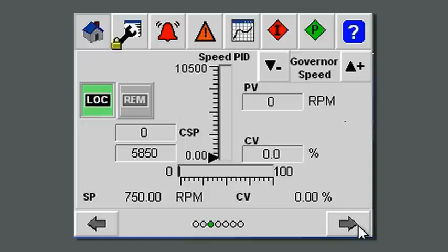The speed PID is the one that actually controls the steam turbine speed. On this screen you see everything about the speed PID that you would normally need during normal operations. It allows you to go in and make changes to set points for speed if you're controlling it directly. If the speed is being driven by a remote set point, that remote set point would be coming in and shown on this particular display.